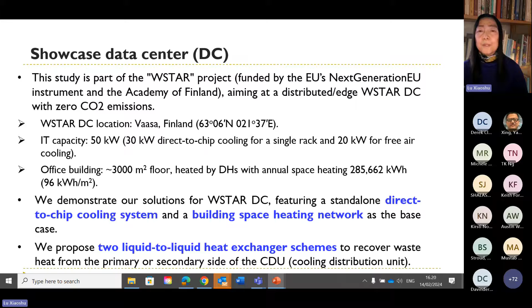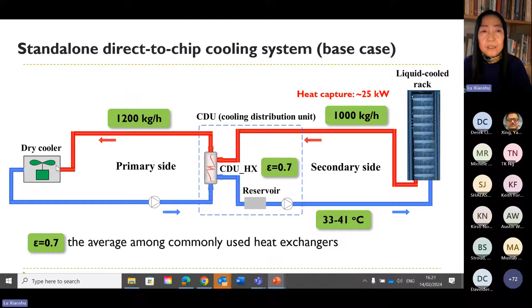So this is the first case, the standard direct-to-chip cooling system as a base case. The middle square represents the CDU heat exchanger. Because we want to be at low cost, we assume the effectiveness of this heat exchanger is 0.7. This is an average among commonly used heat exchangers. So this CDU cools the rack on the secondary side and the interface dry cooler on the primary side. And this is the standard building space heating network.